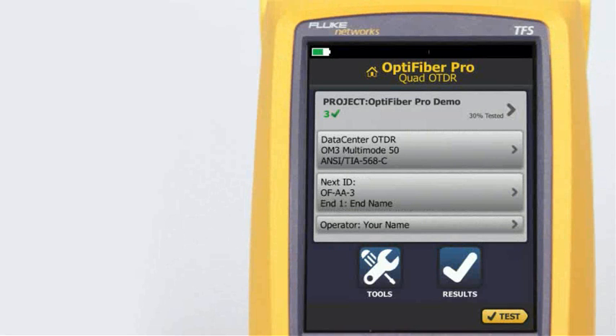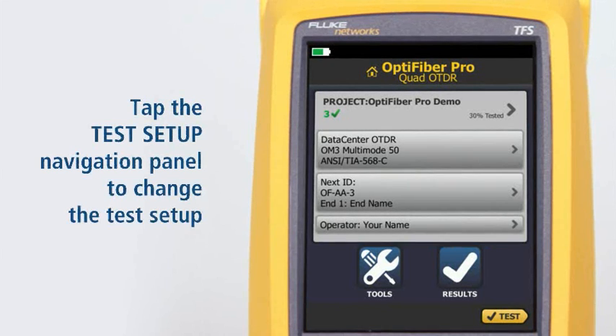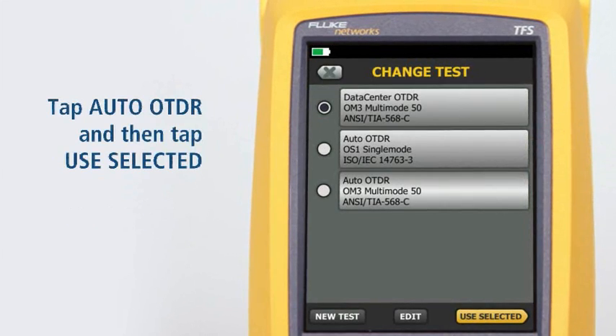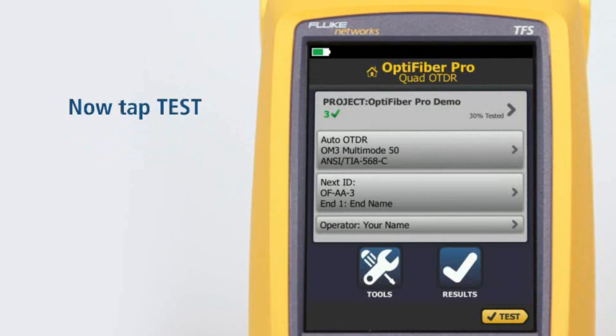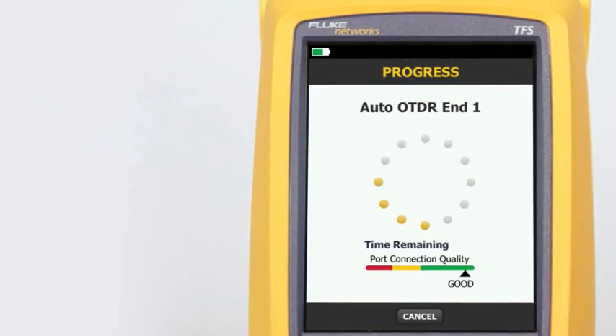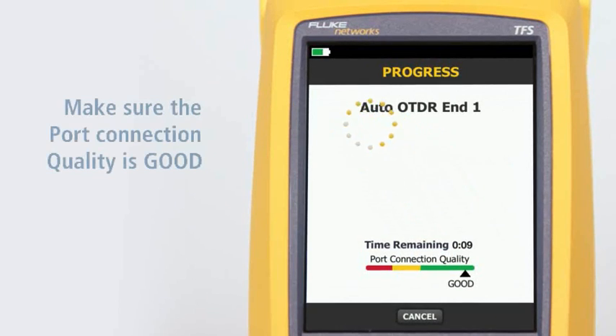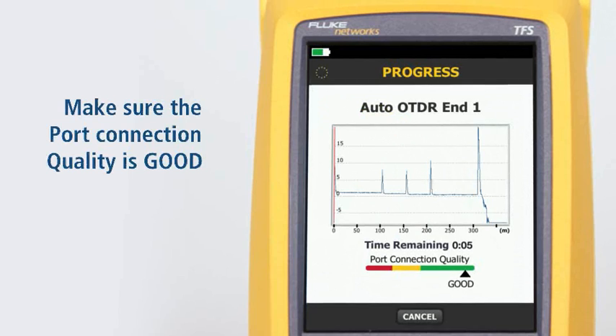The Auto OTDR test mode automatically selects settings that give you the best combination of test time, dynamic range, and resolution. It provides the best view of the events on the cabling. This mode is the easiest to use and is the best choice for most applications. Tap the Test Setup navigation panel to change the test setup. Tap Auto OTDR and tap Use Selected. Now simply tap Test and the tester will determine the best setting to use for the fiber under test. Make sure the port connection quality is good; if it's not good, the tester's ability to properly analyze the fiber may be impaired.